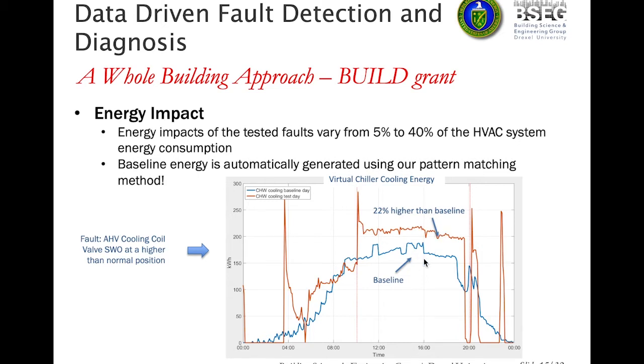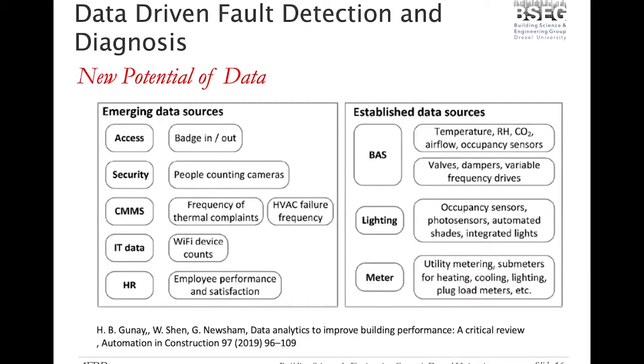For example, this is when we identified a fault occurring. You can clearly see that from the baseline, the energy is around the blue line region, and the red line is when the fault occurred. The energy benefit analysis is kind of a byproduct of such pattern-matching approaches to perform FDD.